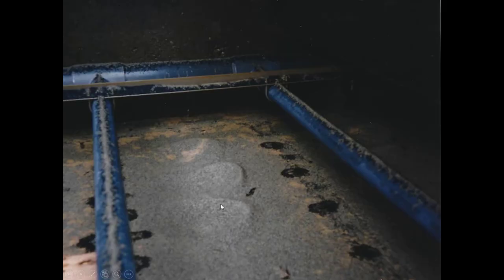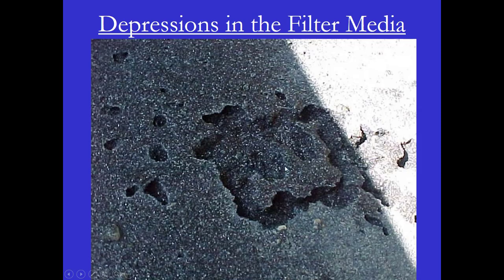Here's an example of some mounds in the filter media — there are mounds here, here, and here. Here are some more examples of depressions in the filter media. You can also see there are some mud balls — there's one right here.